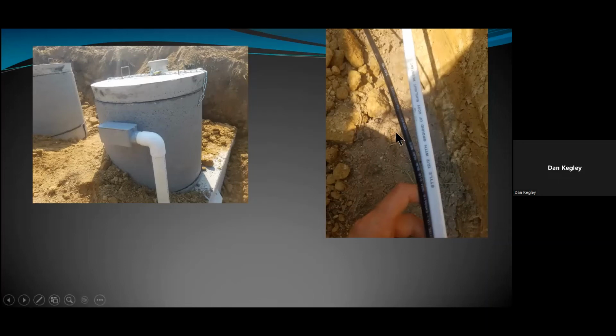And then it looks like the alarm circuit. So this looks like probably a low voltage alarm circuit. And then it should say direct burial. Right here it says DIR-BUR, so that's direct burial cable. On the side there, it does say direct burial cable. So that's another key indicator that you want to look for on low voltage cabling, to make sure it says DIR-BUR, or it'll be spelled out direct burial.